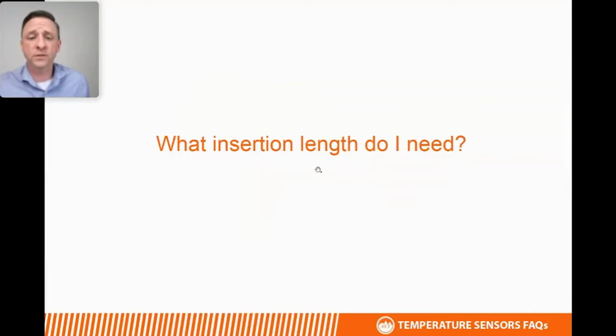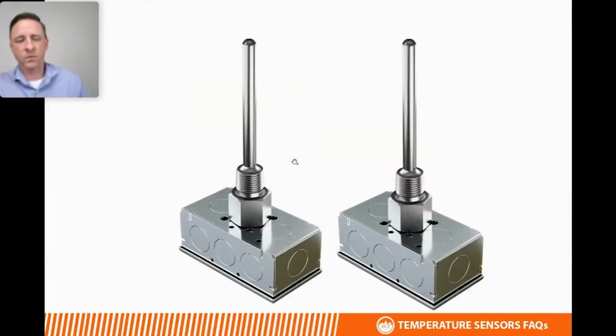Moving on to our immersion sensors. A common question is, what insertion length do I need? We recommend that the tip of the probe be inserted 1/3 to halfway into the pipe. If you're in between lengths or you're not sure which length to use, we'll generally recommend going shorter rather than longer to minimize obstruction of flow in the pipe. We don't want to encourage turbulence or any obstructions to the water flowing through the pipe.